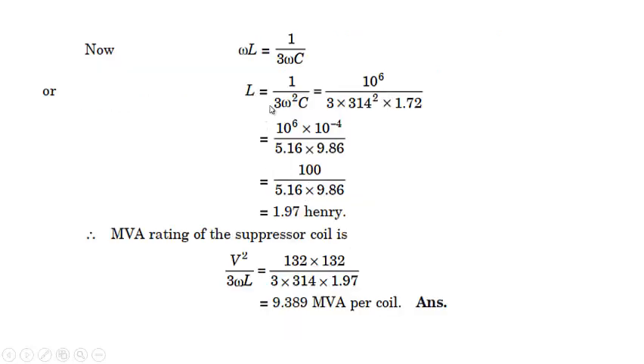So we know that L is equal to 1 by 3 times omega square C, so it comes out to be 1.97 Henry. So MVA rating will be equal to V square by 3 omega L. Actually, this should be V phase square. When you use the line voltage, the 3 comes over here. It comes out to be 9.389 MVA per coil.